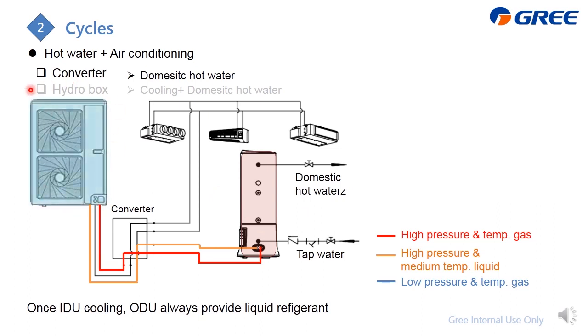And for the indoor unit, if they require cooling, which is cooling plus domestic hot water, then for example, if these two require cooling, we need to send the cold gas, or rather send the refrigerant in liquid, to the indoor unit. After it absorbs heat, which is doing the cooling of the indoor unit, we need to collect the gas back to the outdoor unit. So you can find at this time, this is for cooling and these two are for heating.